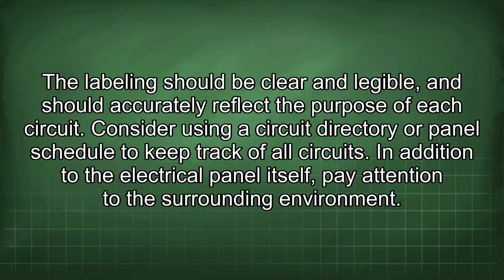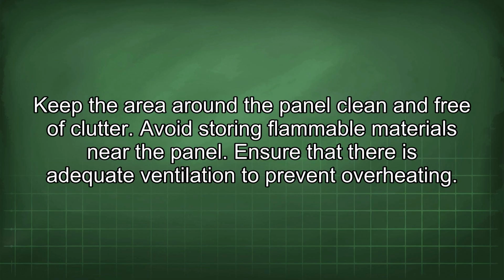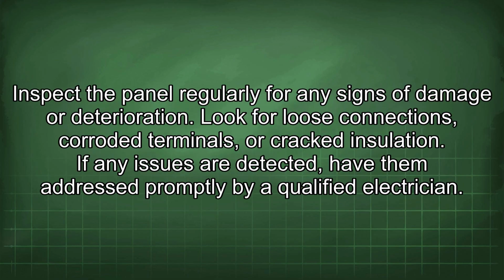In addition to the electrical panel itself, pay attention to the surrounding environment. Keep the area around the panel clean and free of clutter. Avoid storing flammable materials near the panel. Ensure that there is adequate ventilation to prevent overheating. Inspect the panel regularly for any signs of damage or deterioration. Look for loose connections, corroded terminals, or cracked insulation. If any issues are detected, have them addressed promptly by a qualified electrician.